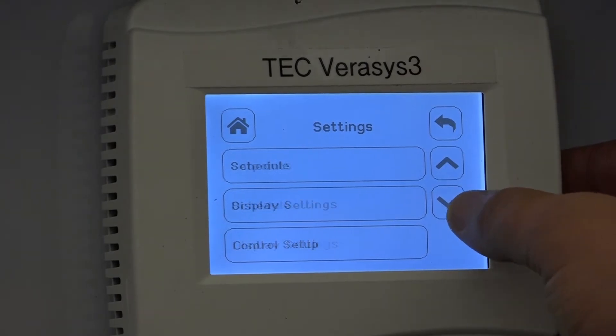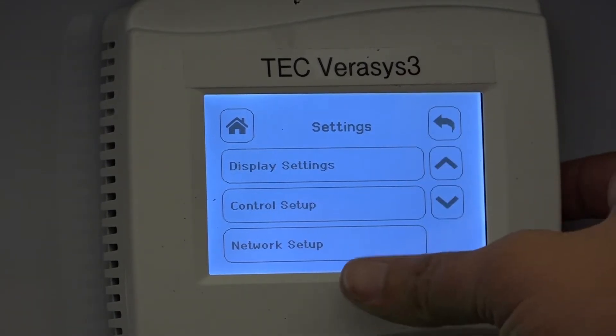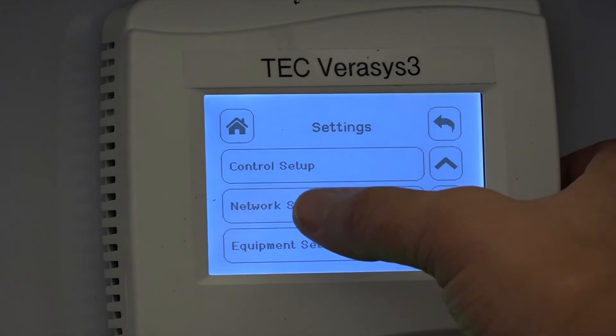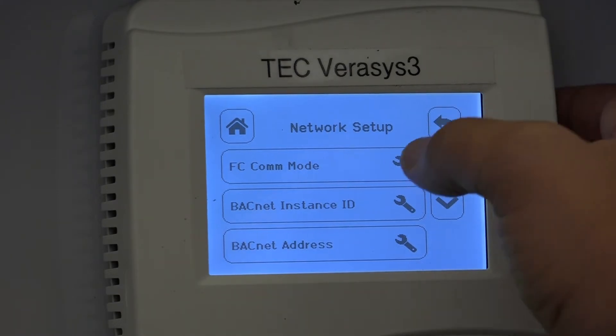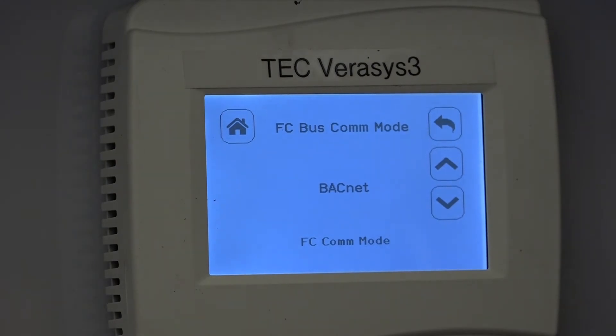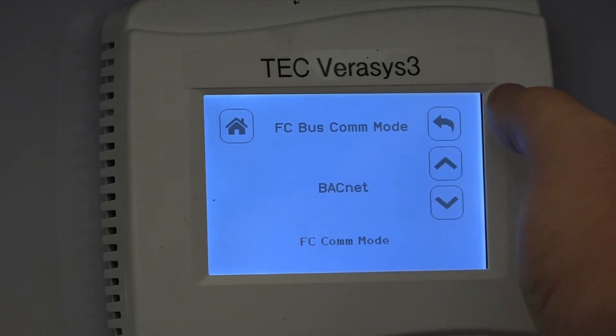Through the up and down arrows you can scroll to the various sub-menus within the TEC. The sub-menu I'm looking for is Network Setup. Through Network Setup, you set your BACnet address and also your communication mode. We need to make sure that the communication mode is set to BACnet. By default it should be, but it could also be set to N2, so we need to verify that it has been set to BACnet.